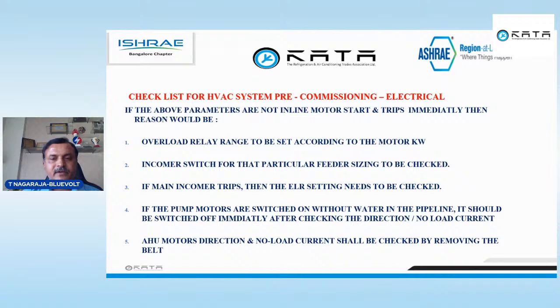Incomer switch sizing for that particular feeder has to be checked again. That's the second point. If the main incomer trips, then the ELR setting needs to be checked. If any one motor switches on, immediately your 400 amps main incomer trips. Sometimes, instead of putting the whole cable through the CT, they put only one phase. Workers will be fitting, and they put the ELR CTs on one phase and go. Then what will happen? Suppose you want to start a 1 kilowatt motor, if you switch on, your main incomer of 600 amps will trip. Why? Because your ELR is sensing.